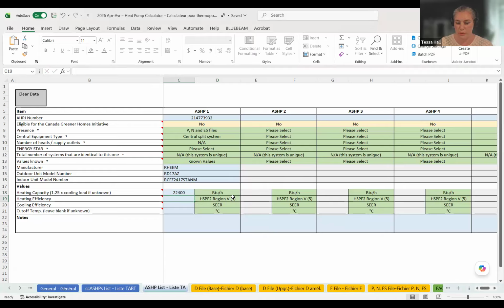This one and this one, we need to be really cautious about making sure we're putting the right inputs in here. Typically I find in the AHRI certificates that the HSPF2 is rated in region 4, so we do need to make sure that we're changing this. In this one it is region 4 and it is 8.5. And then we've got a SEER rating - that is 18.